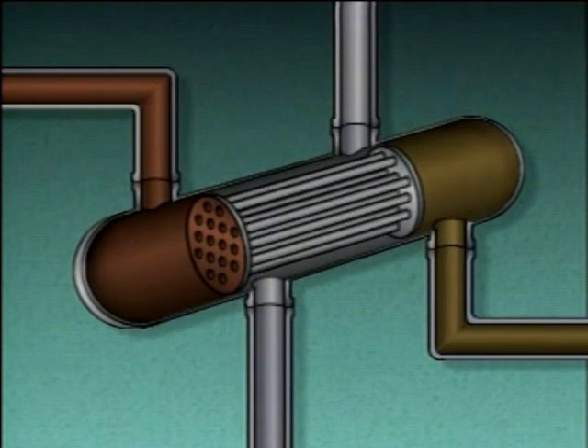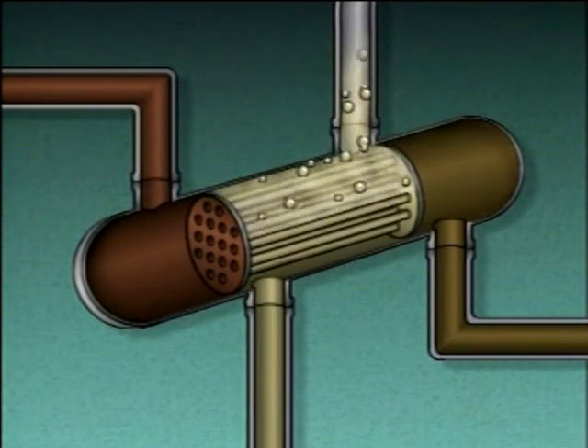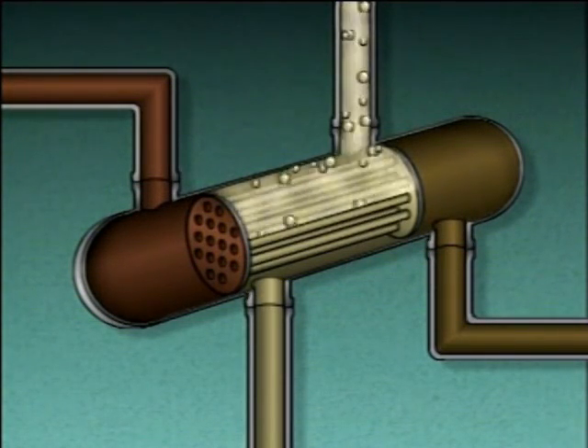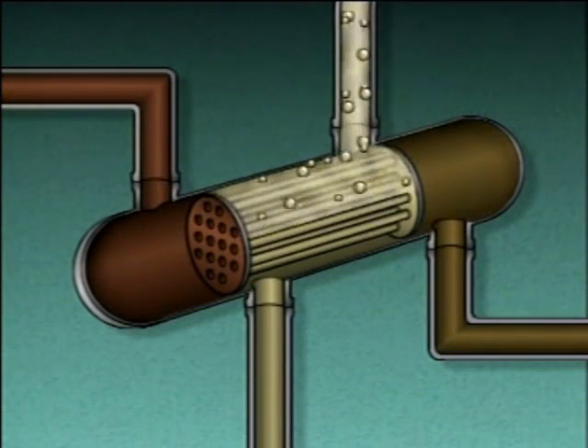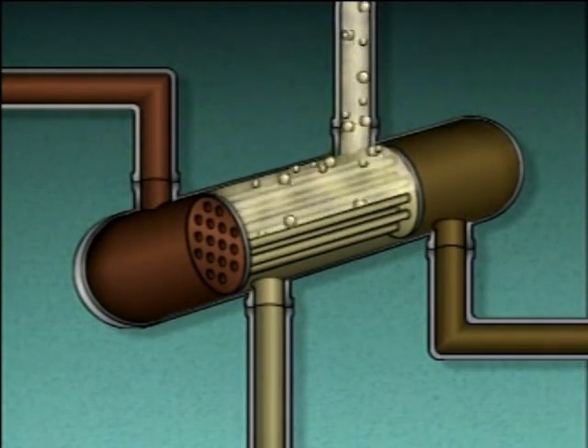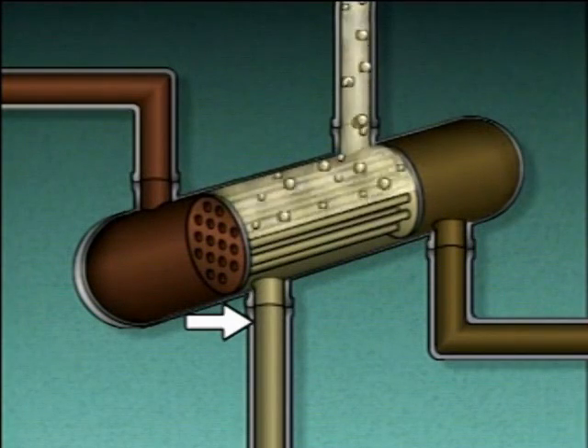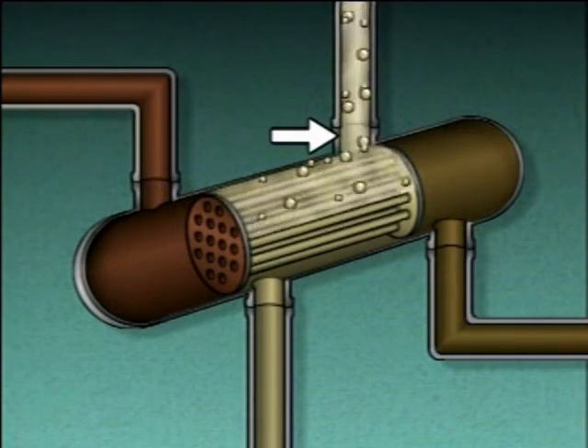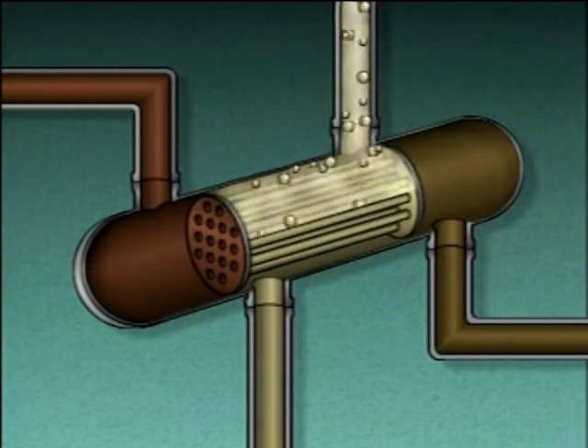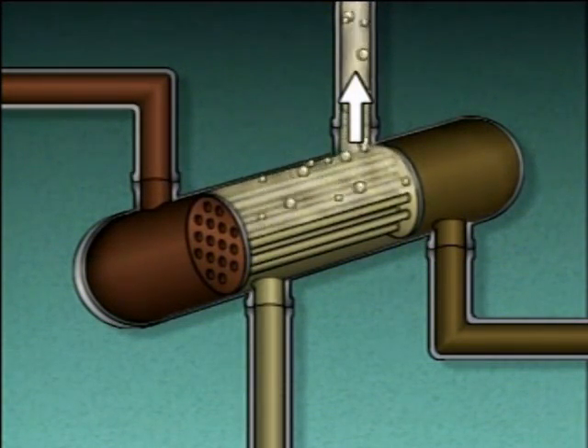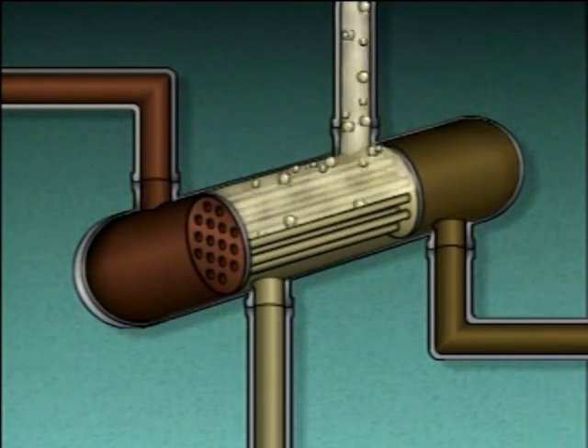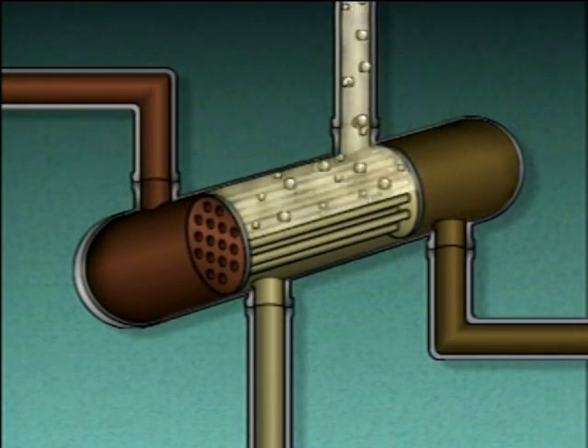The process liquid from the distillation column enters the reboiler's shell and passes around the tubes. Heat from the hot oil vaporizes part of the process liquid. The mixture of liquid and vapor is then returned to the distillation column. The flow of the process liquid and vapor is caused by the difference between the density of the liquid entering the reboiler and the density of the heated mixture returning to the distillation column. The heated mixture in the reboiler is less dense than the liquid coming in from the column, causing the heated mixture to rise out of the reboiler and return to the column, resulting in natural circulation between the reboiler and the distillation column.